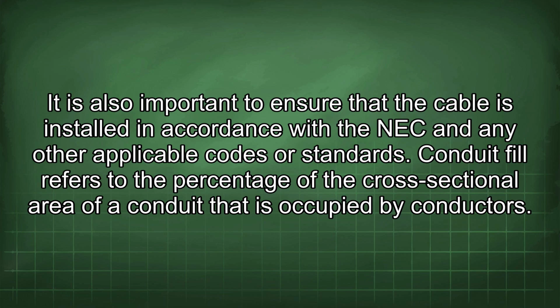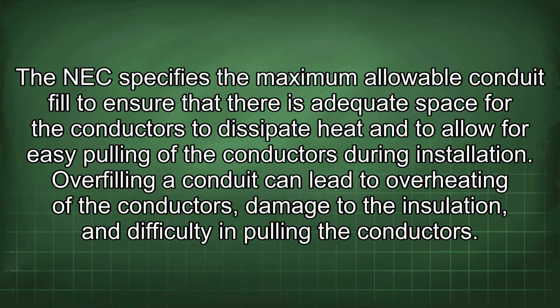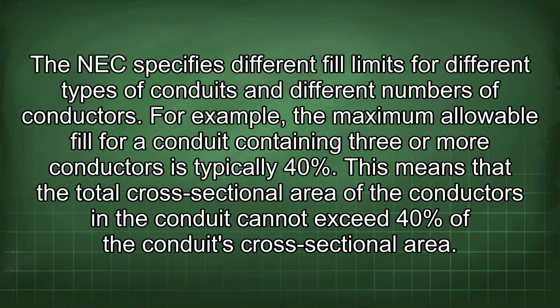Conduit fill refers to the percentage of the cross-sectional area of a conduit that is occupied by conductors. The NEC specifies the maximum allowable conduit fill to ensure that there is adequate space for the conductors to dissipate heat and to allow for easy pulling of the conductors during installation. Overfilling a conduit can lead to overheating of the conductors, damage to the insulation, and difficulty in pulling the conductors. The NEC specifies different fill limits for different types of conduits and different numbers of conductors.